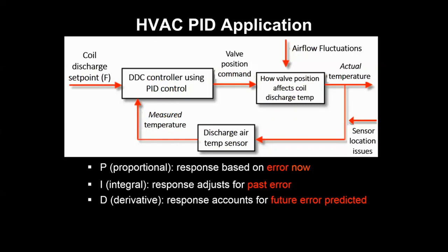So let's look at a simple coil discharge control loop application. Say we have a cooling coil, and we want to discharge so that we have a specific temperature right at the outlet of that coil on the air side in the duct. We have a set point we're telling the controller we want to keep to, say 55 degrees.